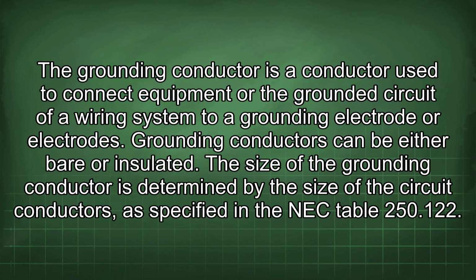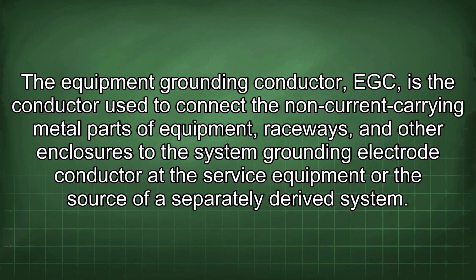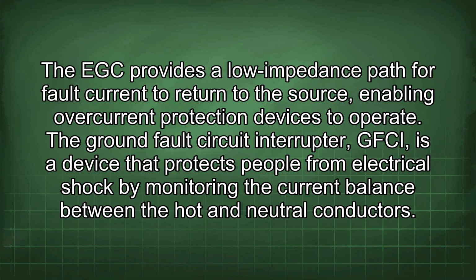The grounding conductor is a conductor used to connect equipment or the grounded circuit of a wiring system to a grounding electrode or electrodes. Grounding conductors can be either bare or insulated. The size of the grounding conductor is determined by the size of the circuit conductors, as specified in NEC Table 250.122. The equipment grounding conductor (EGC) is the conductor used to connect the non-current carrying metal parts of equipment, raceways, and other enclosures to the system grounding electrode conductor at the service equipment or the source of a separately derived system. The EGC provides a low-impedance path for fault current to return to the source, enabling overcurrent protection devices to operate.